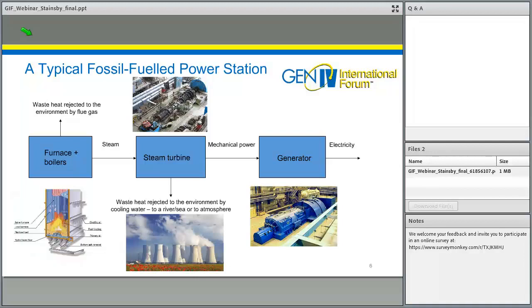We can reduce the temperature a reasonable amount, but if we go too far, then we start to get acid corrosion in the flue structures and things. So we always have to waste some energy up the stack with a combustion plant. The main prime mover or the main engine in a fossil fuel plant is the steam turbine. The steam turbine rejects its waste heat, or its exhaust goes to a condenser. The condenser tends to be cooled by cooling water, which is either drawn from a river or the sea or the ocean, or in the image shown there, it's actually cooled in cooling towers.